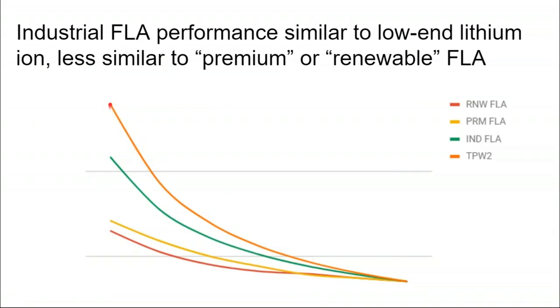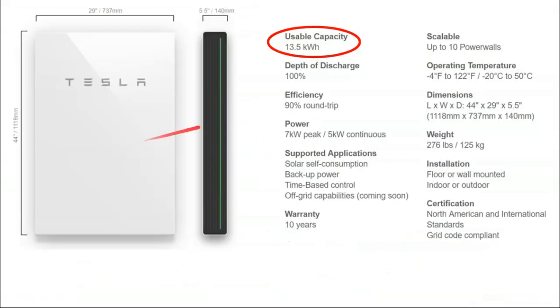Even the Tesla Powerwall, when you start getting into discharge rates of under 2 hours, it starts to tax the limit of the technology. That's why in the Tesla Powerwall spec sheet, it only gives you the ability to drain the 13.5 kilowatt hours in a 2 or 3 hour time frame.